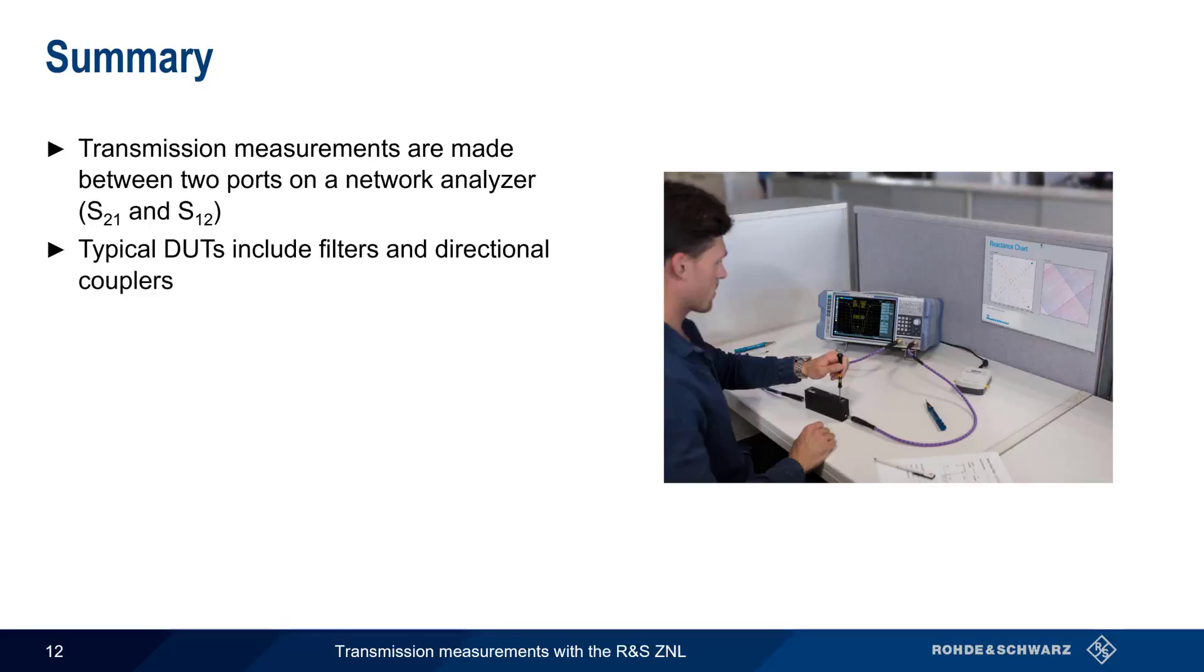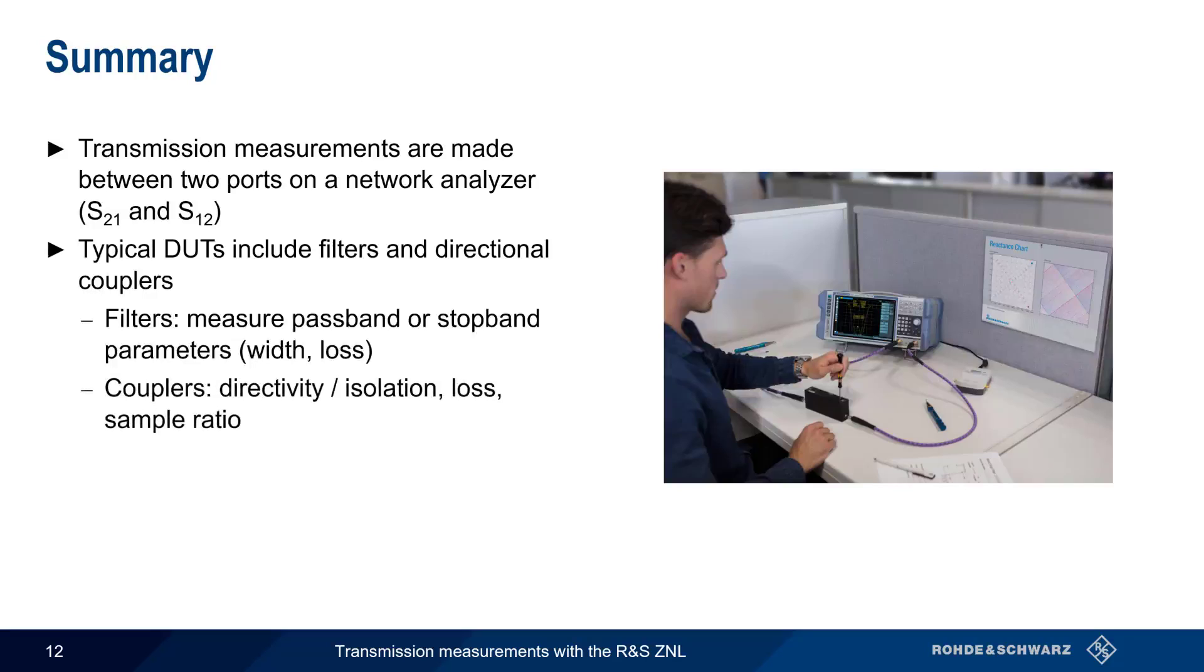For filters, we usually want to measure the width of the passband or stopband, as well as the loss inside and outside of these bands. For couplers, we often look at the directivity or isolation of the coupler, as well as how much signal appears at the sample port. And lastly, we can use markers and automatic measurement functions to improve both the accuracy and the speed of our measurements.